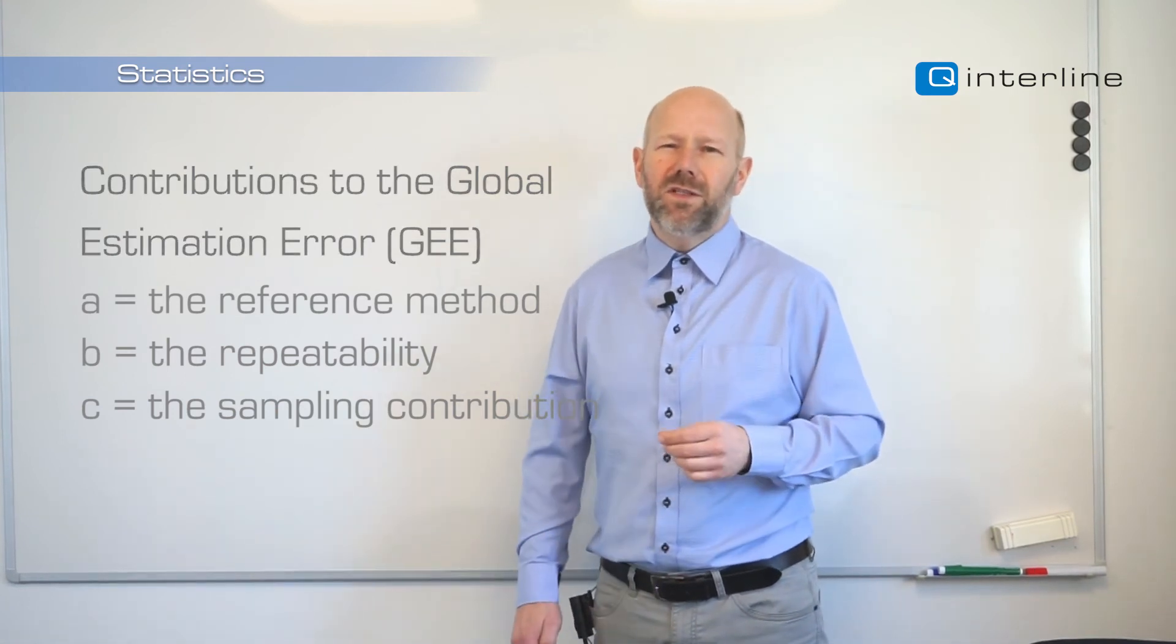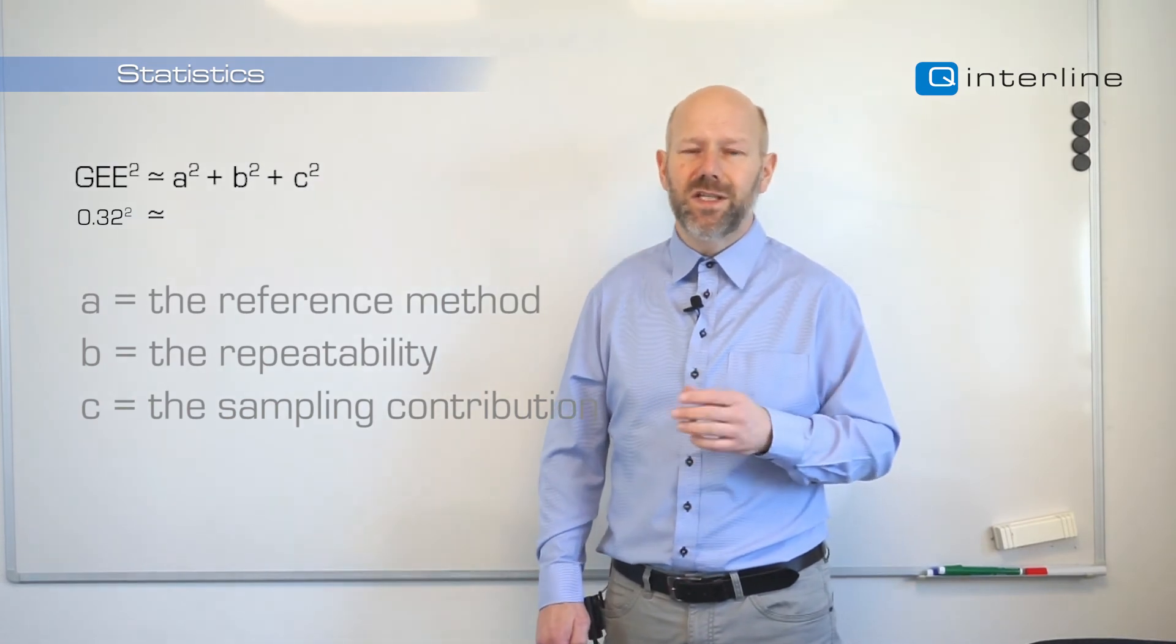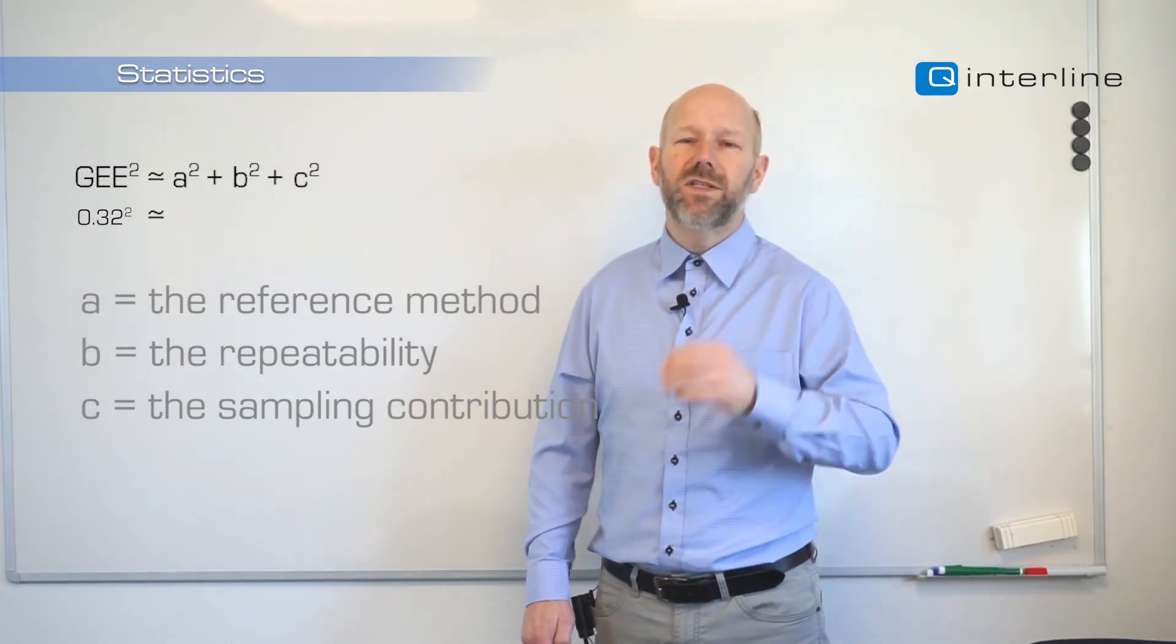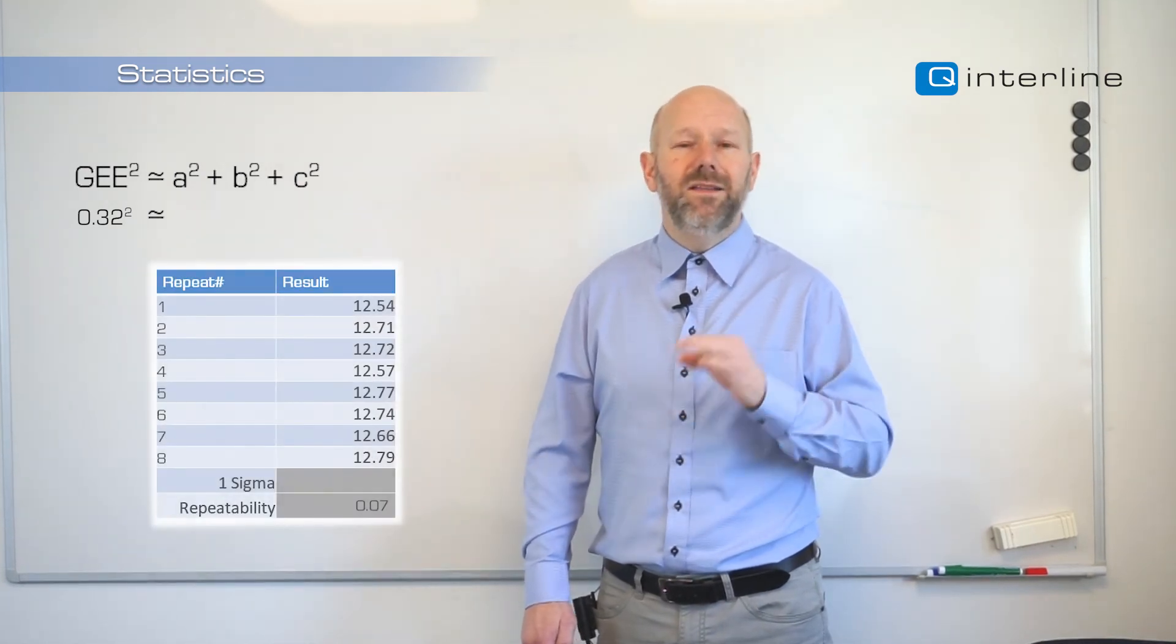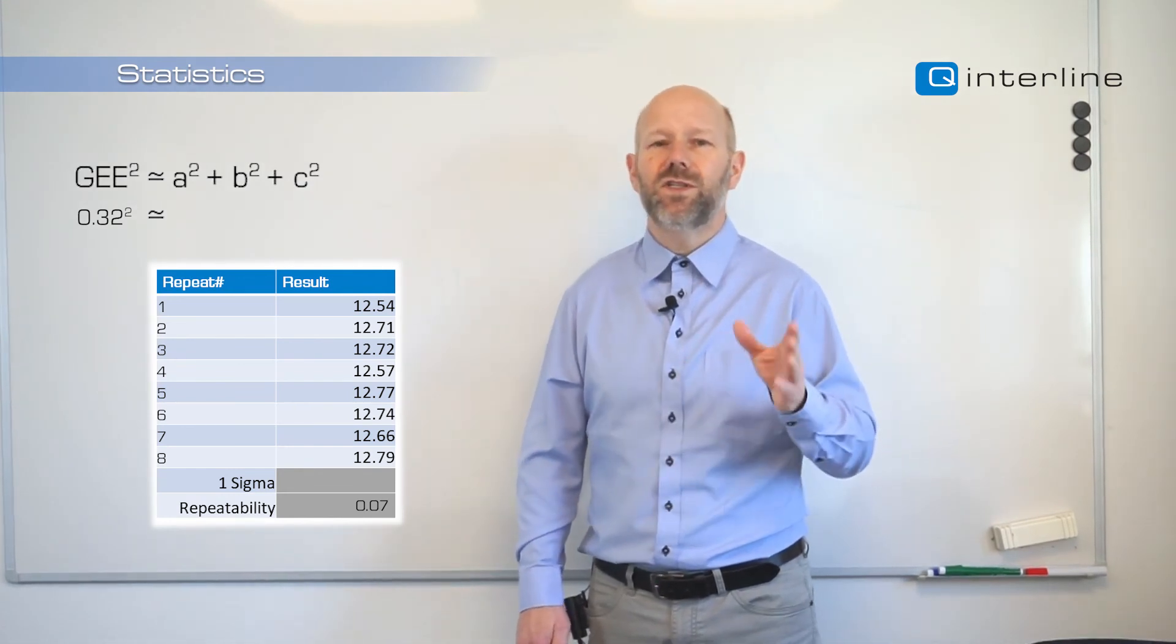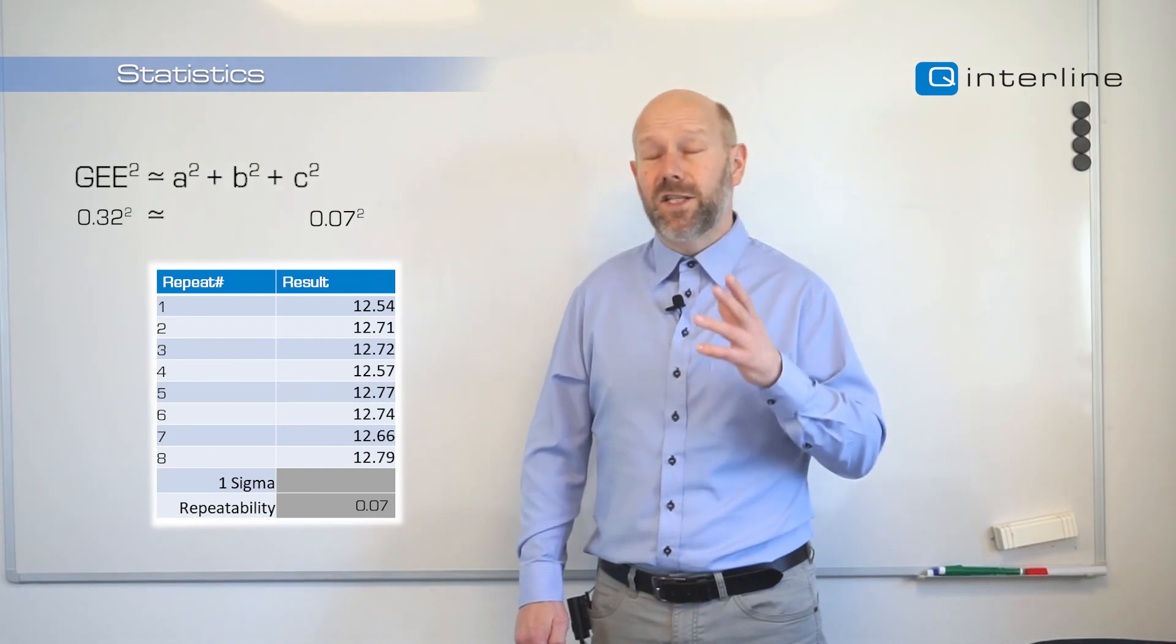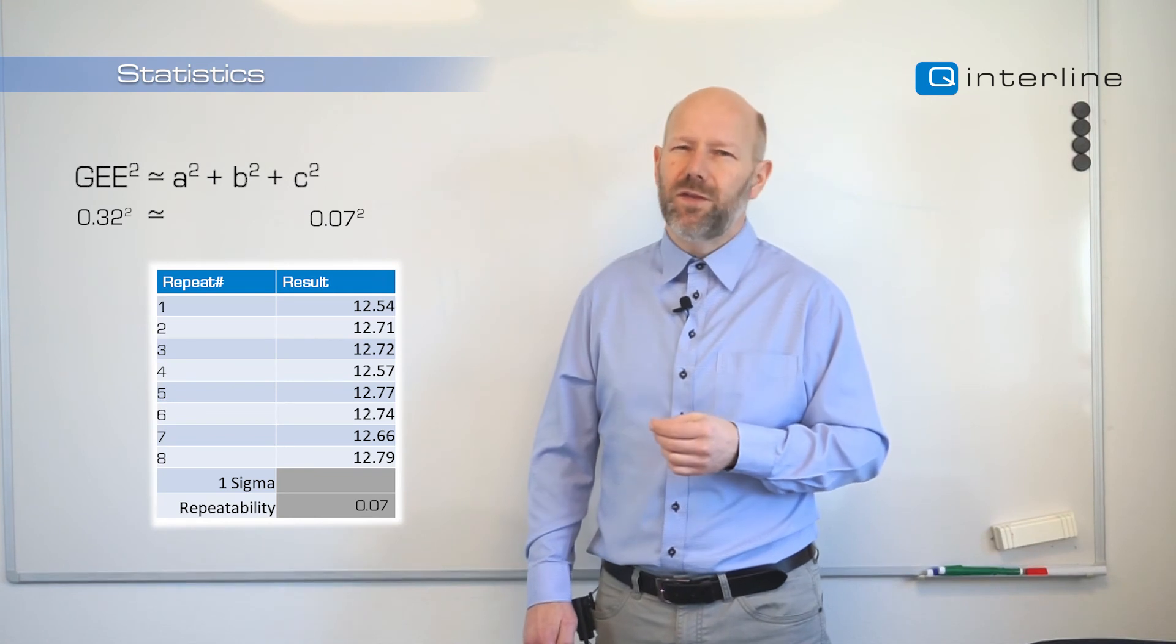The link between these three can be seen in this formula. So the question is, does it really add up? Well, the first thing we can do is test repeatability. Simply leave the same sample in the analyzer and run it eight times. In this case, we see that we ran the sample eight times and the standard deviation was 0.07. So the 0.07 repeatability does not really explain a majority of the 0.32. So there must be other things.